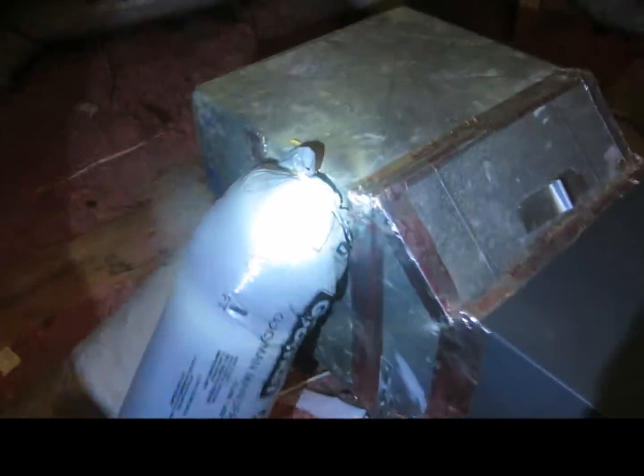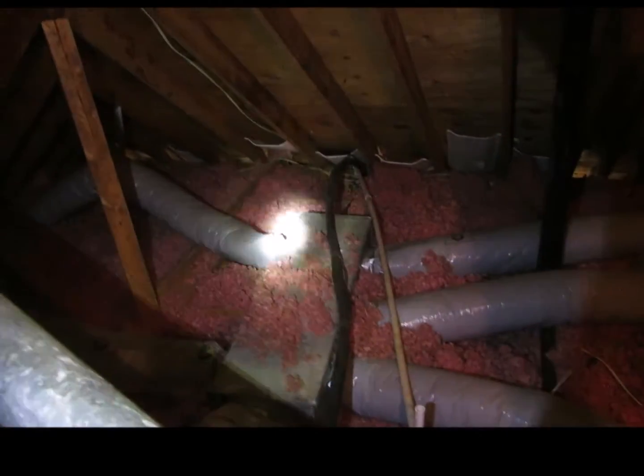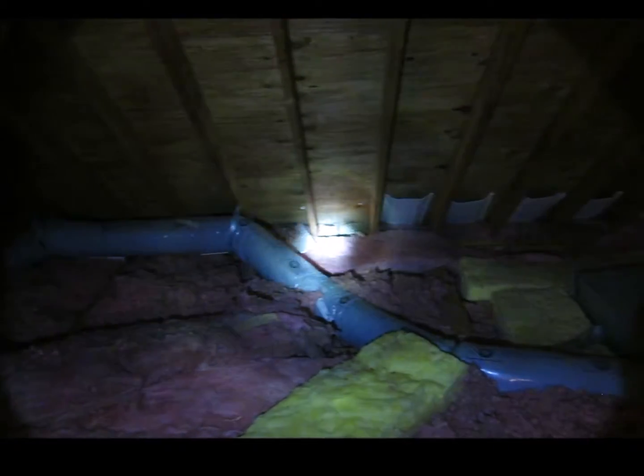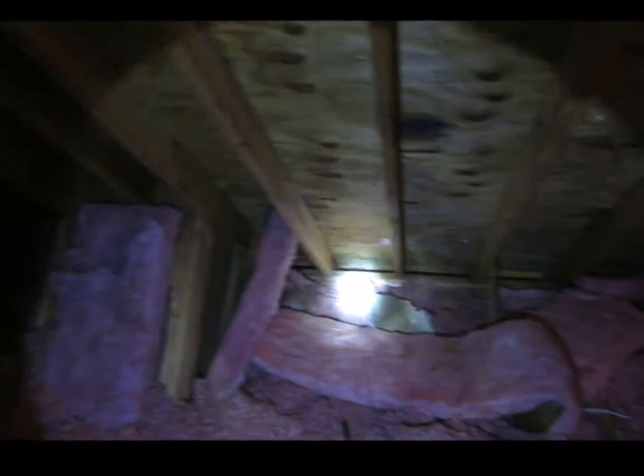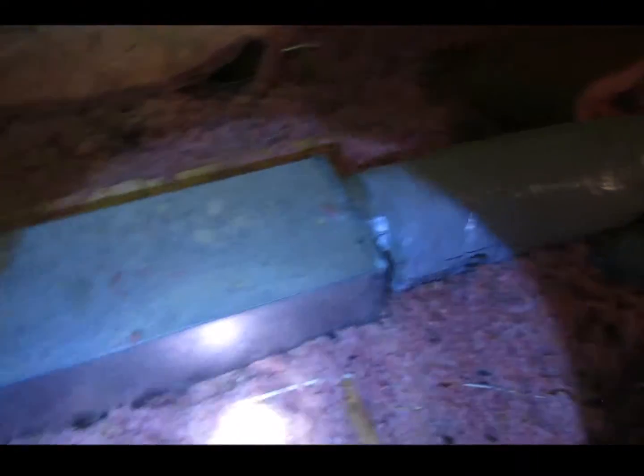Additionally, these air ducts are not sealed, so we're losing probably 20% of our conditioned air into the attic. There's a lot of ducts here and they're not sealed. The insulation is in disarray. It should be repaired. The baffles are also in disarray or altogether missing in some areas. The air sealing into the ceiling for the electrical and the HVAC is also not sealed.